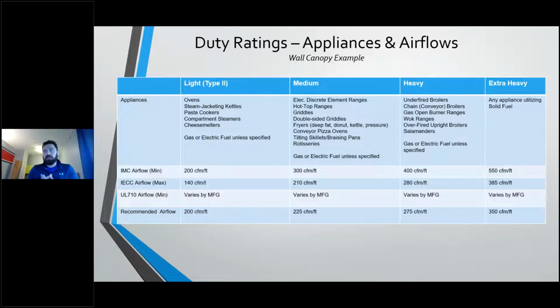This is going to vary by manufacturer, but what I always keep in mind when I'm talking about UL 710 minimums is that these are perfect lab conditions that they were testing in. So I would never recommend designing a system at a UL 710 minimum airflow. I would try to find somewhere in between based on your history and your recommendations. So if you asked me where I would design a medium or heavy duty hood, I wouldn't design it at a UL 710 minimum because that's way too small. But I also wouldn't design it at an IMC 400 CFM per foot because the hood is going to be UL 710 listed. So I would recommend sizing this at about 275 CFM per foot.